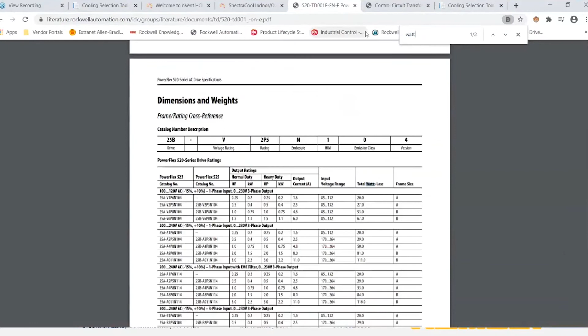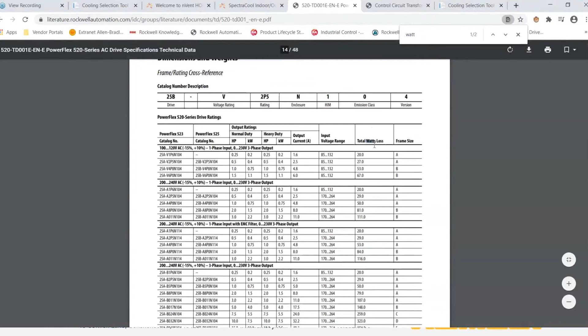For this example, I'll pick a PowerFlex drive, the 520 series, one of our most common ones. If you go to the technical document on almost any Rockwell product that dissipates heat, you can search for either watts or heat loss, and it'll come up. Here you can see all the different drives in the second column from the right, telling you exactly how much heat you're losing per drive. Let's pick a 30 amp, 480 volt drive. My heat loss is 387 watts.